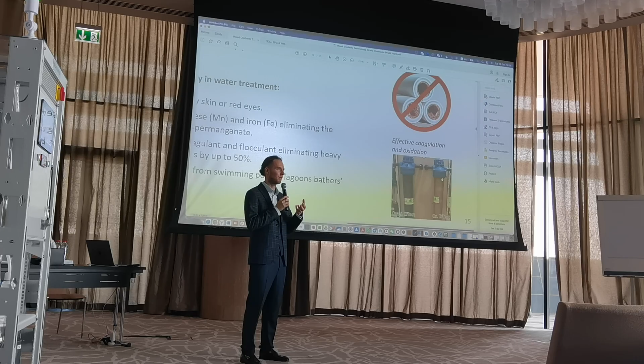Sodium hypochlorite usually contains salt, sodium chloride. Besides active chlorine, it has water and table salt. So when you dose it into the network, it forms sludge. It's well known - if you look at the non-return valve used to dose sodium hypochlorite, within a year it becomes very clogged with salts and slime. The same happens in the network: dosing it creates sludge, which becomes food for microbes again. Here, you inject only pure gases into the water, so it doesn't increase TDS at all - TDS stays the same.